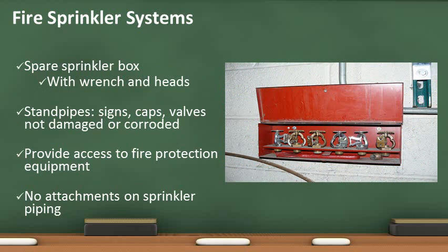All sprinkler systems are required to have a box with spare sprinkler heads and a wrench. The sprinklers shall be representative of the sprinkler heads currently in use in the system.